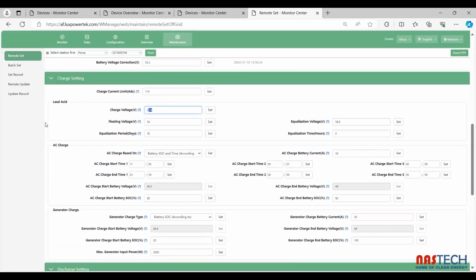Charging my batteries. So these are the lead acid settings on the parameters of the batteries. I want to, for example, if you're in Namibia or Saudi Arabia, you want to charge your batteries during the day. Okay, I'm going to set this charge over. I might not actually change this too much. Yeah, you can set it here. Charge my battery in. This specific person is actually charging from Eskom. You set this to charge from Eskom. I would typically start with a 00 on that side.